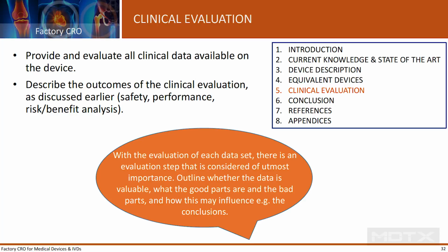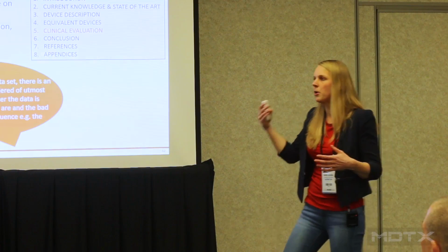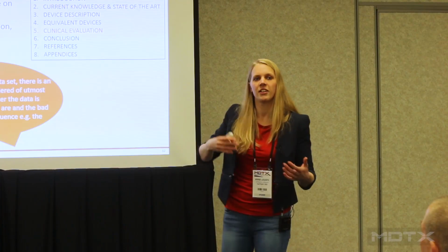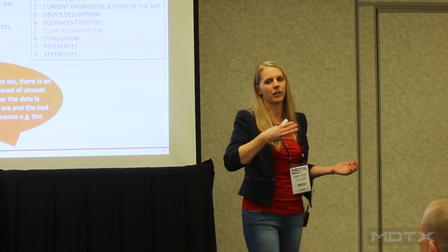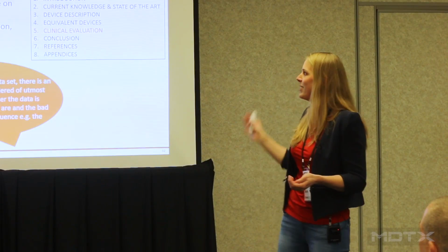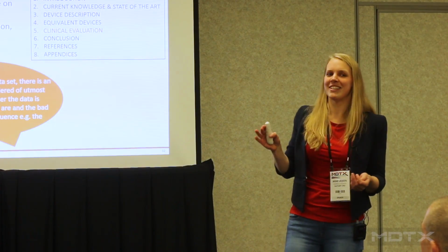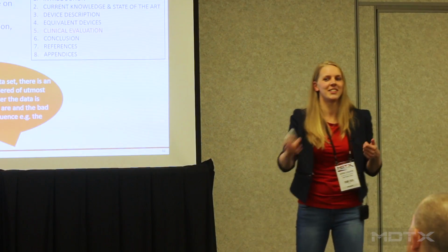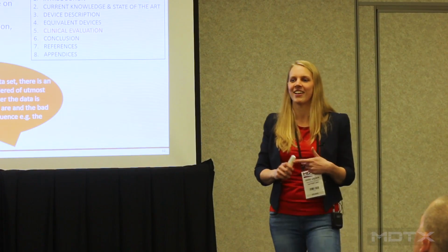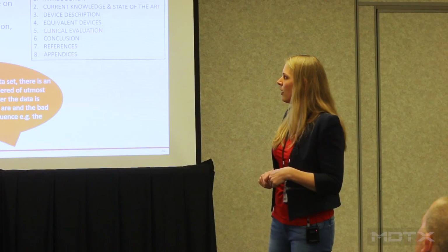And then your clinical evaluation. Here, all those data come together. Here, you provide the relevant preclinical data, your pre-market clinical data, your post-market clinical data, your device recalls, your CAPAs. You can implement all of it here. But do write towards those three essential requirements: the safety analysis, the performance analysis, and the risk analysis.